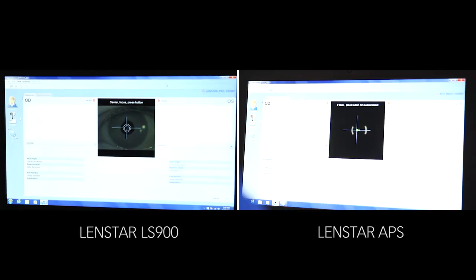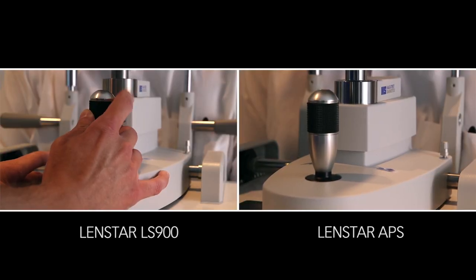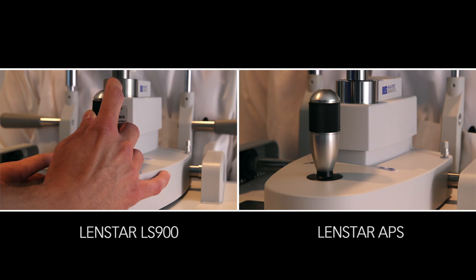To access the fine alignment screen, the operator of both models uses a single click of the joystick. Adjustments are made until the green indicator light appears. The Lenstar LS900 operator captures the first scan by clicking the joystick button.